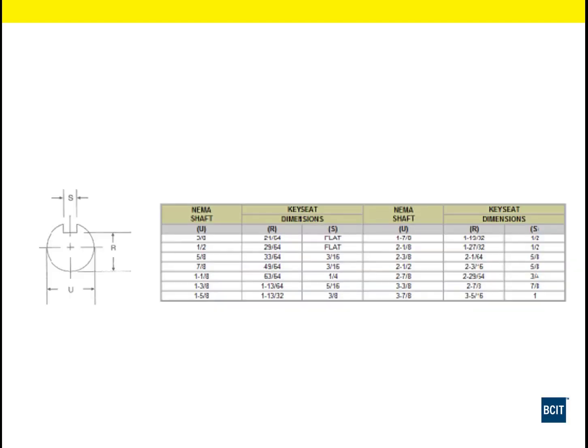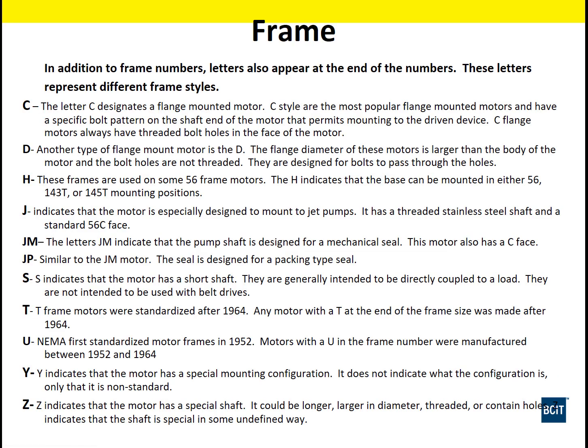Then this is a little detail on the shaft dimensions. When we look at some of those letter codes that we referenced from the frame code, this is a keyway in this shaft. This is the end of the motor shaft. That shows us the dimensions of all that motor shaft: the width of the key, from the opposite side of the shaft to the depth of the key, and then the diameter of the shaft. Here are those letter codes. I'm not going to read the whole thing. If you want to take a screenshot and have a look at it later, that's pretty good.